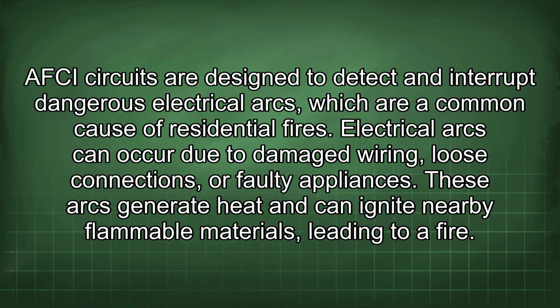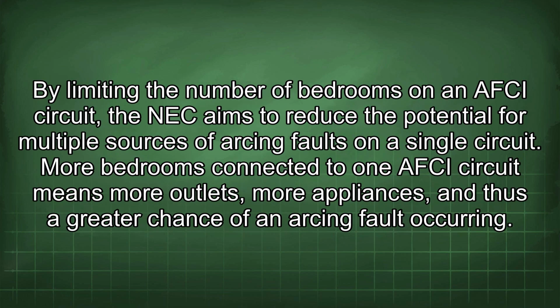Electrical arcs can occur due to damaged wiring, loose connections, or faulty appliances. These arcs generate heat and can ignite nearby flammable materials, leading to a fire. By limiting the number of bedrooms on an AFCI circuit, the NEC aims to reduce the potential for multiple sources of arcing faults on a single circuit.